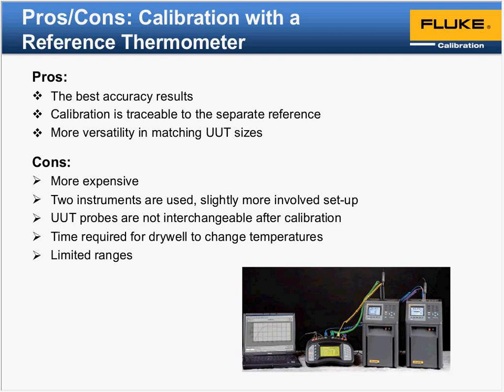What depth did you insert the sensor into the Drywell? That's a really great question. There's a rule of thumb taught to me on immersion depth to help negate any stem conduction errors. You want to go a multiple of the diameter of the probe, plus the length of the sensor. That typically applies to RTDs, and I usually assume the sensor of an RTD is the active length, which may vary, up to 1.5 inches.